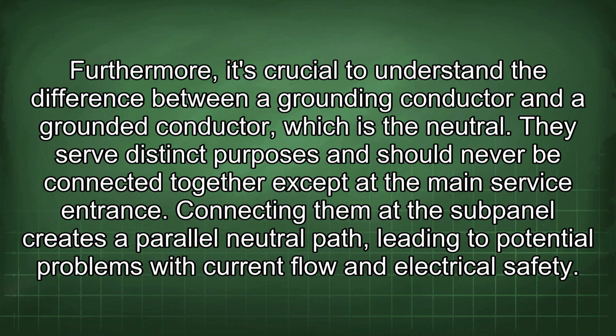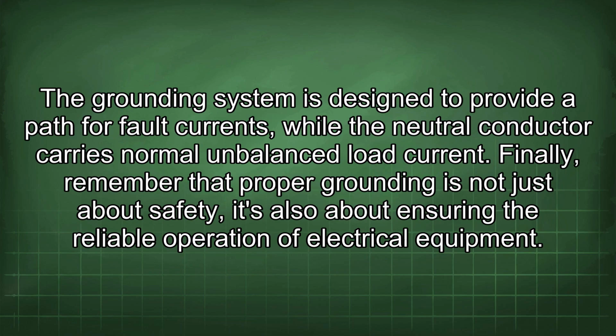Furthermore, it's crucial to understand the difference between a grounding conductor and a grounded conductor, which is the neutral. They serve distinct purposes and should never be connected together except at the main service entrance. Connecting them at the subpanel creates a parallel neutral path, leading to potential problems with current flow and electrical safety. The grounding system is designed to provide a path for fault currents, while the neutral conductor carries normal unbalanced load current.